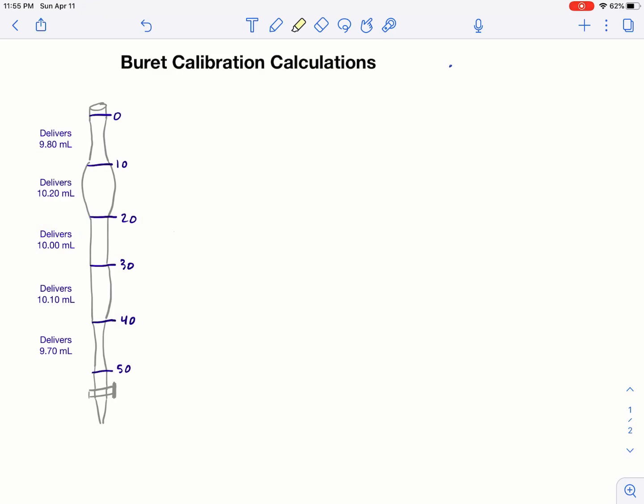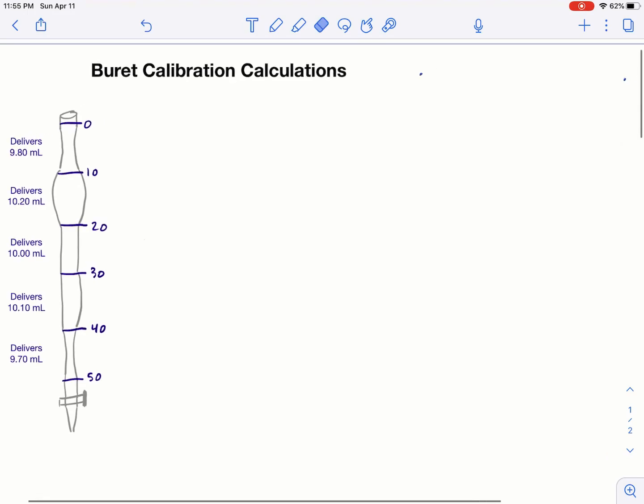The lab stipulates that you dispense these different volumes and weigh the water that comes out and calculate a correction from that. And so the correction looks like this.